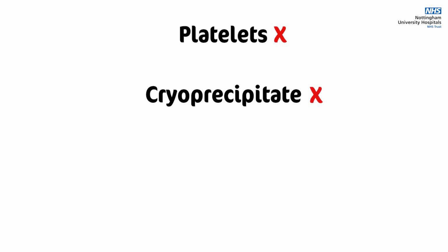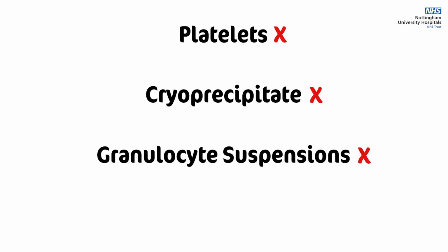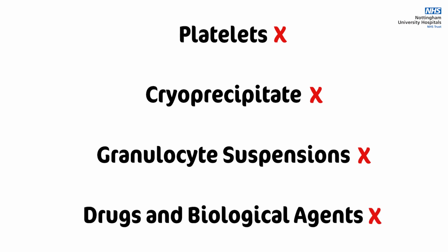The user must demonstrate knowledge of which products and solutions cannot be warmed within the device. Platelets. Platelets can bond to the inner surfaces of the disposable set, reducing the amount of platelets reaching the patient and consequently affect the device operation. Cryoprecipitate. Cryoprecipitate should not run through a rapid infuser to prevent dilution. Granulocyte suspensions. Granulocytes are fragile cells and therefore should not be administered through a rapid infuser. Drugs and biological agents cannot be administered via the Belmont.